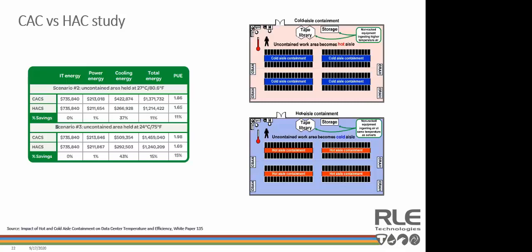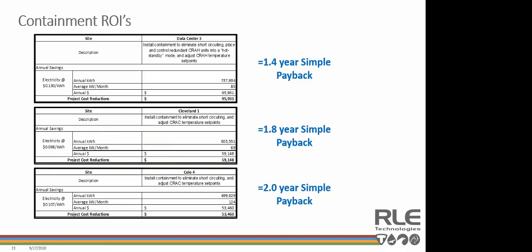In the end, the percentage of savings between hot aisle and cold aisle containment can vary based on the size and shape of your data center, along with many other aspects. In addition to this, you can see that as the uncontained area temperature increases, cold aisle containment actually gets more efficient due to a higher return air temperature to the CRAC units. Now I'll hand it back to Tim to talk about ROIs of the containment solutions. Thanks, James.